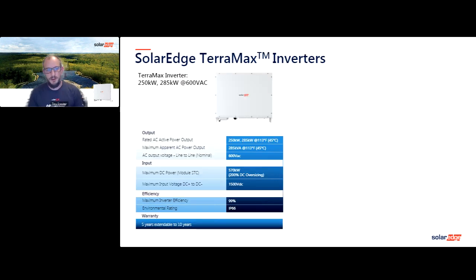So first, let's talk about the inverter. The one we focus on for community solar and large scale is our 600V output inverter, at 250 kilowatts and 285 kilowatts—two different power classes. We also have a 690V option, which is better suited for larger scale plants. The 600V market is fine-tuned based on the supply chain around AC disconnects, circuit breakers, and transformers. 600V is the sweet spot for a lot of the other AC balance of system components. So we have two power classes, the 250 and 285.